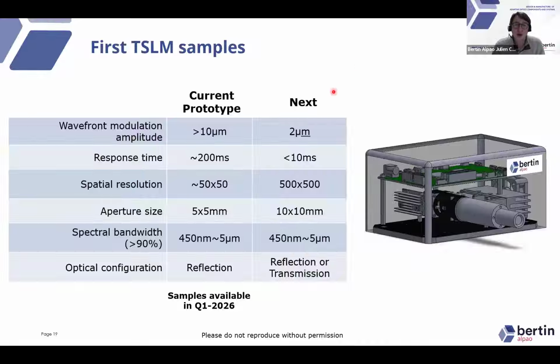And the next step, well, it will depend on the demand. Because we can tune the parameters, if you prefer to keep the large amplitude, or increase or reduce the response time, we will not do the same tuning. But currently, the baseline is to have the first product with a smaller amplitude of modulation, because it's what the SLM user needs, and to reduce the response time below 10 milliseconds. We think we can go close to 1 millisecond, and to increase the spatial resolution a lot, so you can do a more complex wavefront.